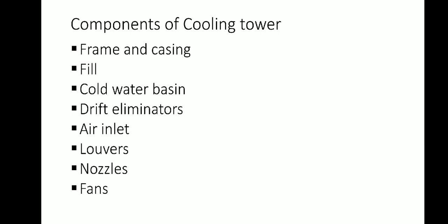Then fans. Both axial and centrifugal fans are used in towers. Generally, propeller fans are used in induced draft towers, and both propeller and centrifugal fans are found in forced draft towers. Depending upon their size, propeller fans can either be fixed or variable pitch. A fan having non-automatic adjustable pitch blades permits the same fan to be used over a wide range of kilowatts, with the fan adjusted to deliver the desired airflow at the lowest power consumption. Automatic variable pitch blades can vary airflow in response to changing load conditions.